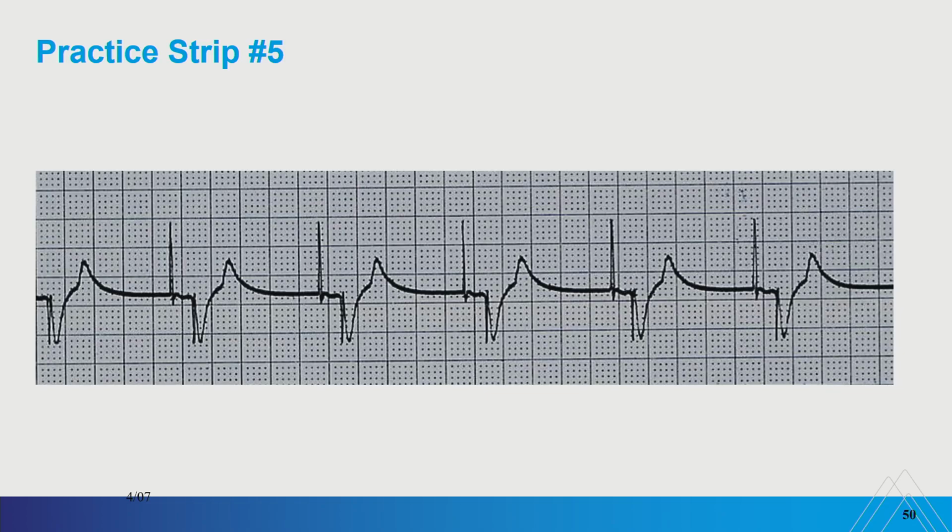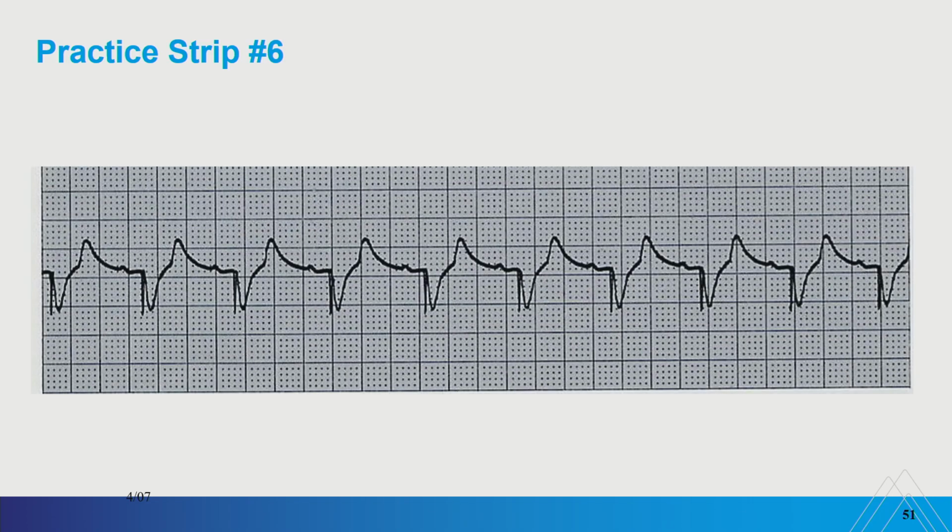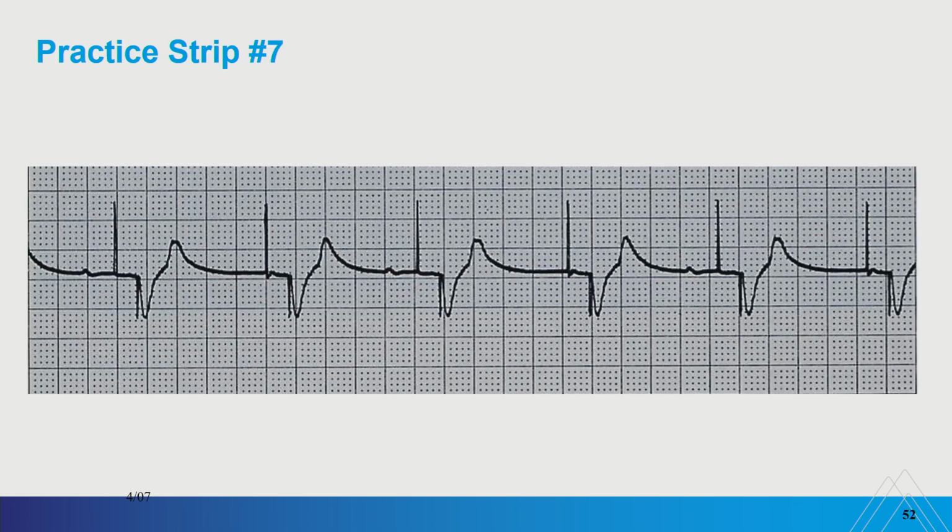What kind of pacing? Good. What mode? On this one. What mode? DDD. How do I know it's DDD? Right, because I'm tracking the atrium. I know that because I triggered the secondary clock to count down the 170 milliseconds, and then I pace the ventricle. It's very consistent with the atrial activity. This is a DDD pacemaker, not a DVI pacemaker, DDD.